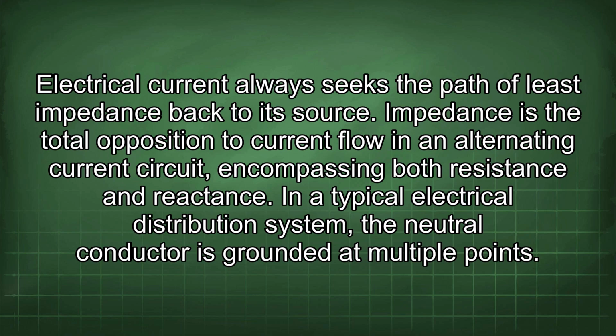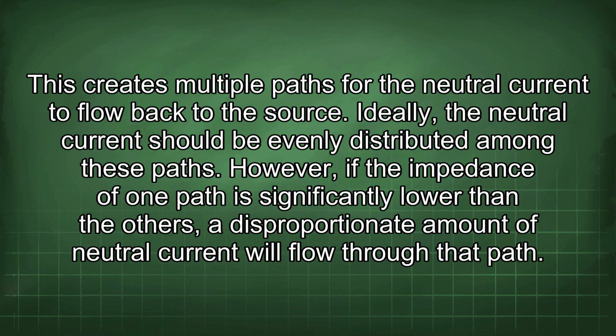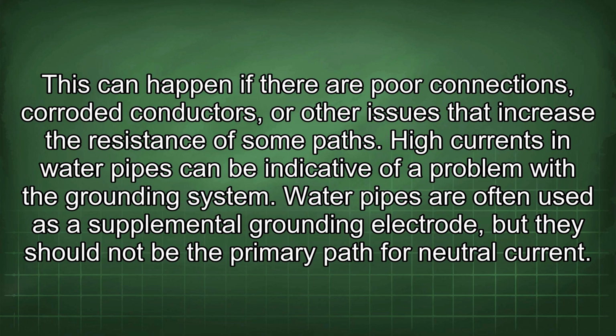In a typical electrical distribution system, the neutral conductor is grounded at multiple points. This creates multiple paths for the neutral current to flow back to the source. Ideally, the neutral current should be evenly distributed among these paths. However, if the impedance of one path is significantly lower than the others, a disproportionate amount of neutral current will flow through that path. This can happen if there are poor connections, corroded conductors, or other issues that increase the resistance of some paths. High currents in water pipes can be indicative of a problem with the grounding system.